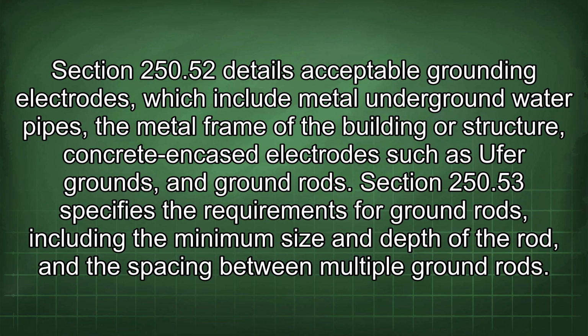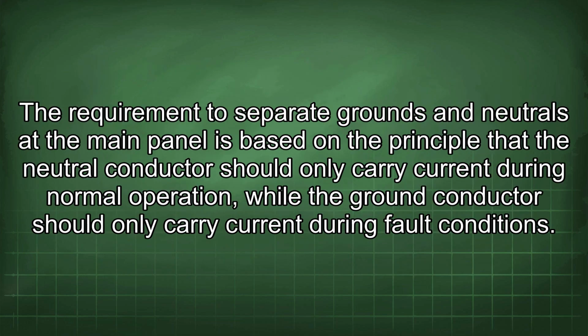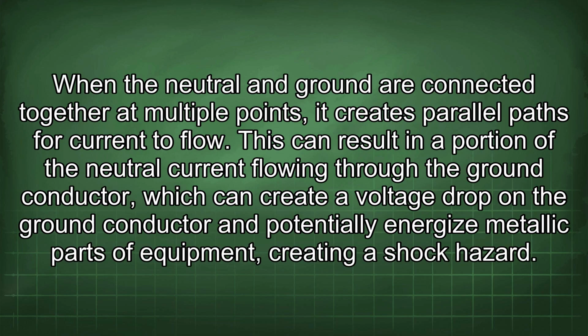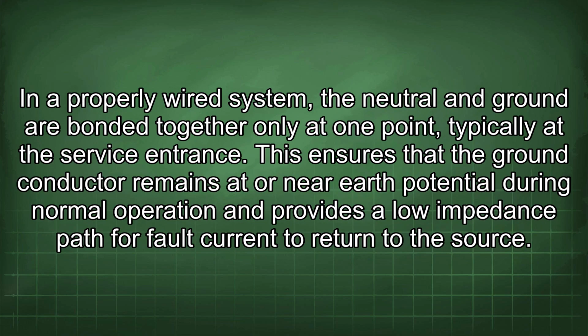The requirement to separate grounds and neutrals at the main panel is based on the principle that the neutral conductor should only carry current during normal operation, while the ground conductor should only carry current during fault conditions. When the neutral and ground are connected together at multiple points, it creates parallel paths for current to flow. This can result in a portion of the neutral current flowing through the ground conductor, which can create a voltage drop on the ground conductor and potentially energize metallic parts of equipment, creating a shock hazard. In a properly wired system, the neutral and ground are bonded together only at one point, typically at the service entrance.